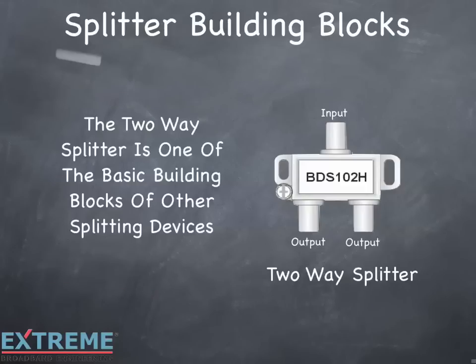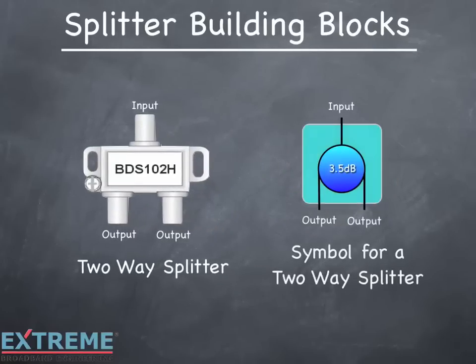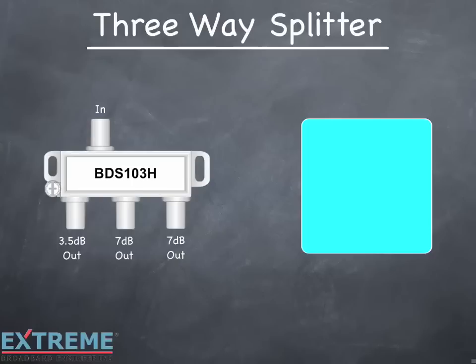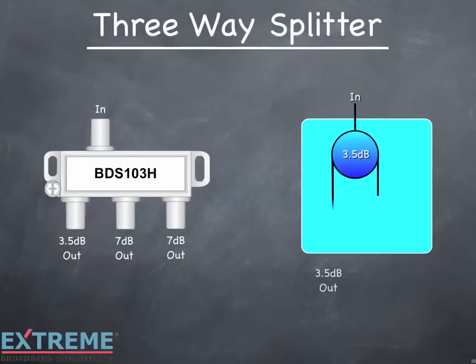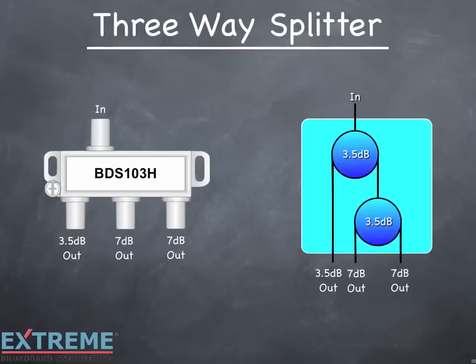The two-way splitter is one of the basic building blocks of other splitting devices. On the left we're showing a two-way splitter; on the right is the symbol equivalent indicating the input, 3.5 dB of loss, and two outputs. Using this symbol, let's build other splitting devices. On the left is an unbalanced three-way splitter with one leg losing 3.5 dB and the other two losing 7 dB. The 3.5 dB leg is fed directly from one leg of a two-way splitter. Adding one more two-way splitter to the other output port gives a 7 dB loss. So a three-way splitter is made up of two two-way splitters.